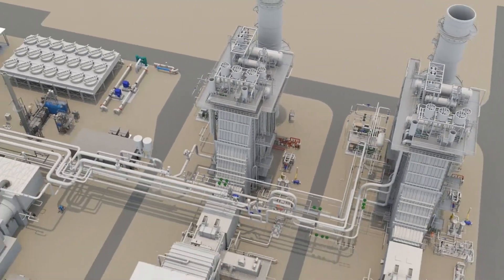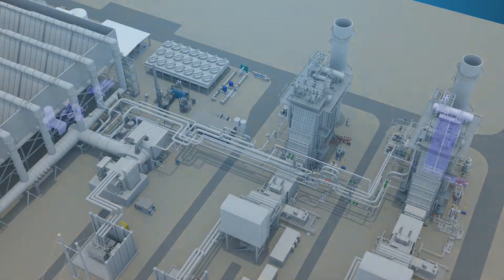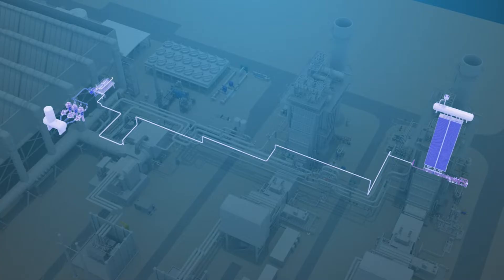The LP drum is also filled prior to starting the boiler feed water pump by the condensate system, as the LP drum provides the suction flow to the feed pump.